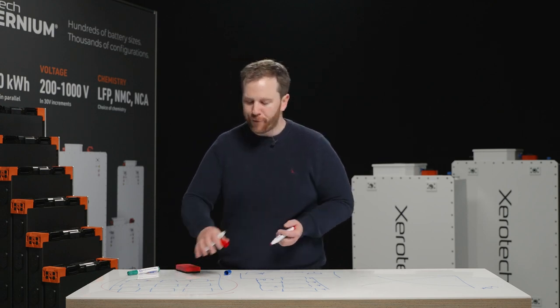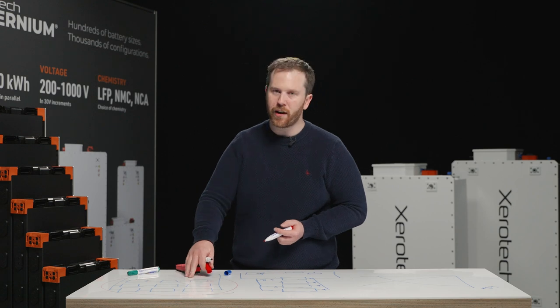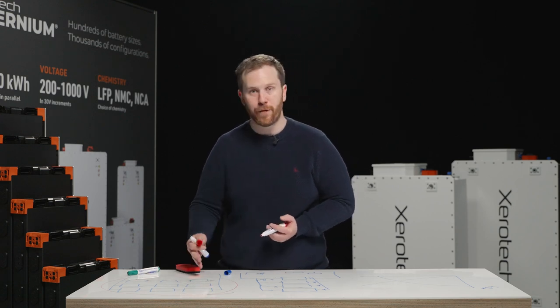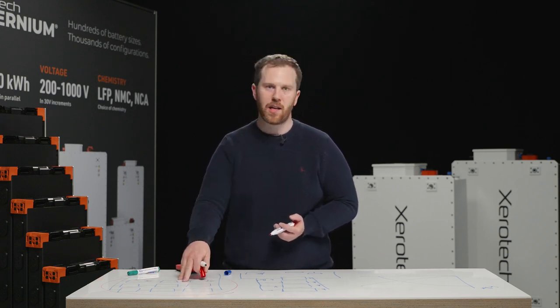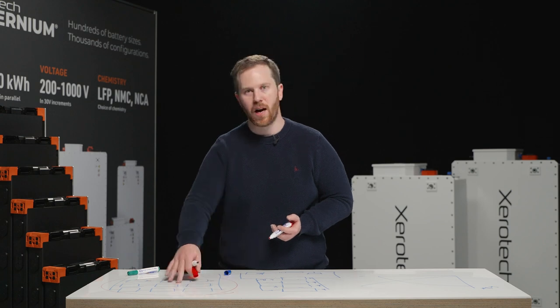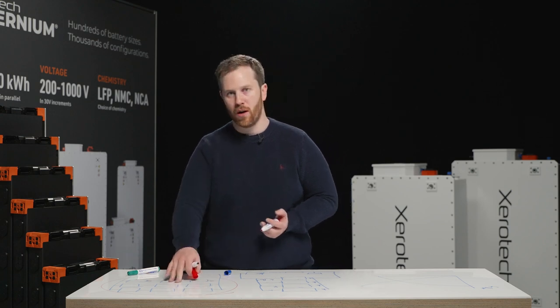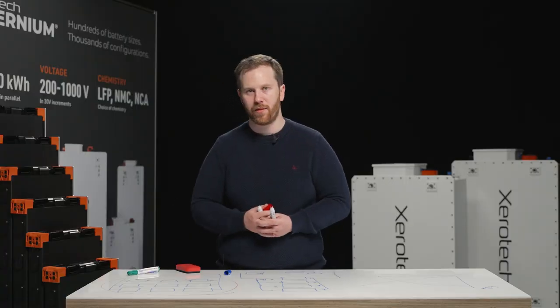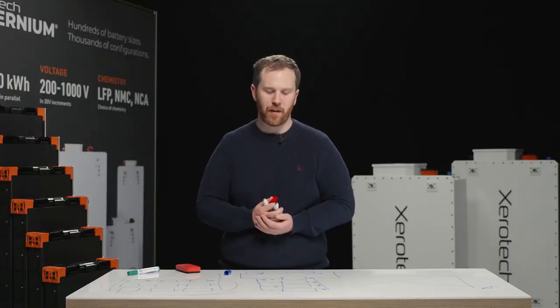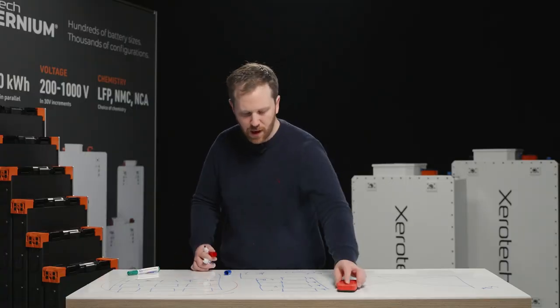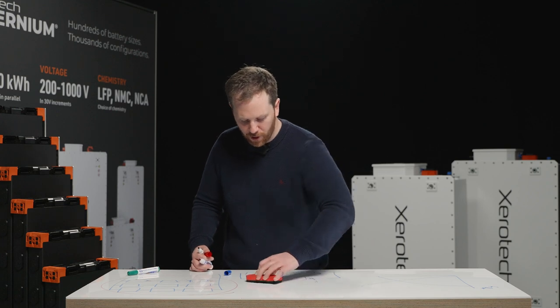make it work. And for larger scale systems, we strongly recommend putting in coolant filters in case there is contamination in the system, so that you cannot compromise a large network of battery systems. So there's a lot of considerations there to watch out for. So please contact Xerotech if you're unsure about a large multi-pack installation. But for the vast majority of applications, it will just be a single pack in a loop.